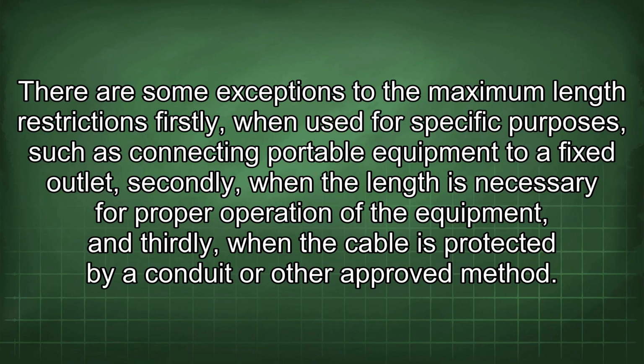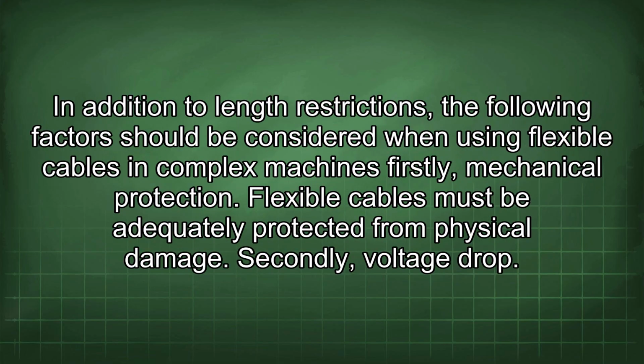Firstly, when used for specific purposes, such as connecting portable equipment to a fixed outlet. Secondly, when the length is necessary for proper operation of the equipment. And thirdly, when the cable is protected by a conduit or other approved method. In addition to length restrictions, the following factors should be considered when using flexible cables in complex machines.